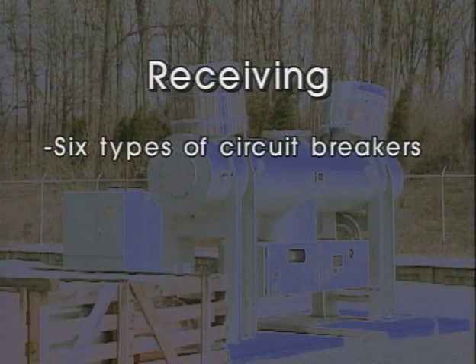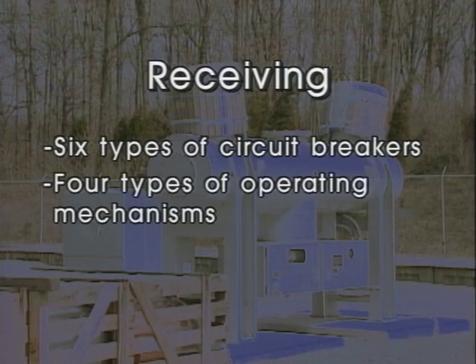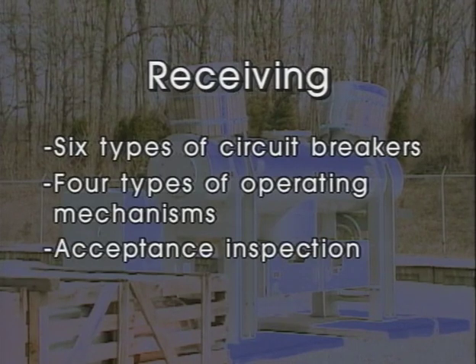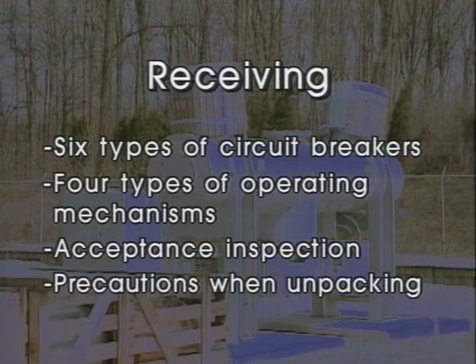First, we'll identify 6 different types of circuit breakers that you might receive, because some inspections and tests apply only to a specific type of breaker. In addition, we'll identify 4 types of circuit breaker operating mechanisms for the same reason. Then we'll look at some of the typical steps of a circuit breaker acceptance inspection. We'll also look at the precautions you should take when unpacking and opening circuit breaker components.